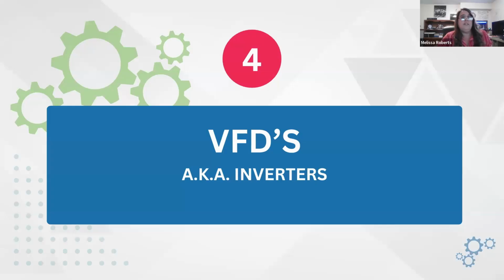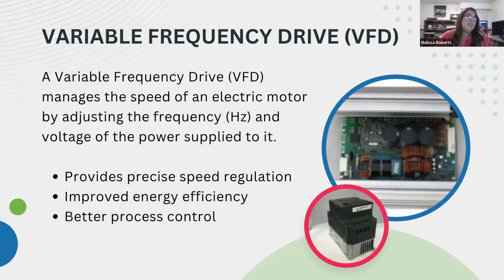Okay, so VFDs, inverters, we hear them called different things. We're going to dive into those and explain how they work. A variable frequency drive, or VFD, manages the speed of an electric motor by adjusting the frequency, or hertz, and the voltage of the power supplied to it. It provides precise speed regulation, improved energy efficiency, and better process control of your machines.